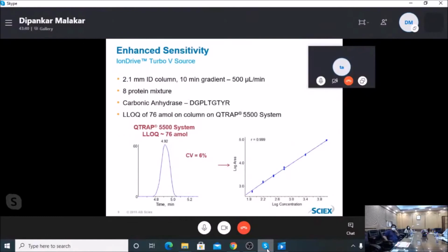This is a high flow application with a flow rate typically of 500 microliters per minute with a 10 minute gradient. The ID of the column is 2.1 millimeter. This is a carbonic anhydrase peptide, and we are getting very good low level detection, like 76 attomole on column injection, as our LLOQ.